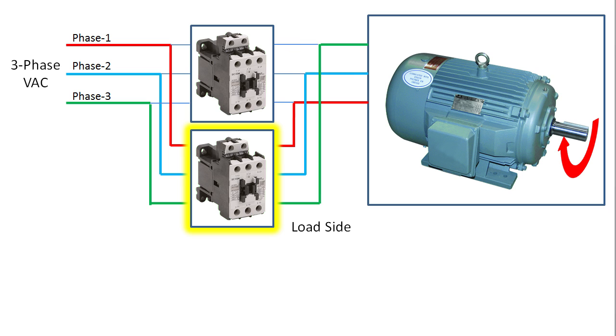What happens if you accidentally engage both contactors? Well, now you are shorting out two of the three phases of your power system and that usually makes bad things happen. The way you prevent that is to add interlocks.